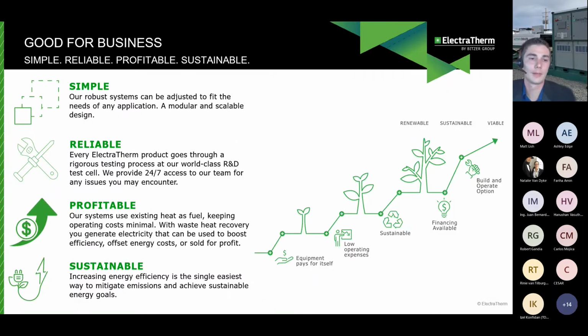So the units are very good for business because they're simple, reliable, profitable, and sustainable. The units are very robust. Again, I compare them more to refrigeration compressor type technology. They're more of a set it and forget it type appliance. So when they have heat, the units come online and start producing power. When that heat source disappears, the units go offline. When it returns, they start up again. It can be a hands-off approach.